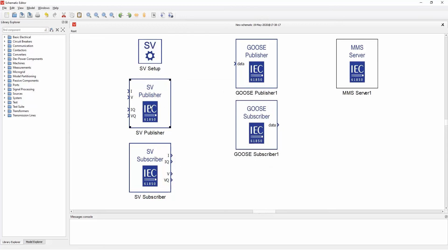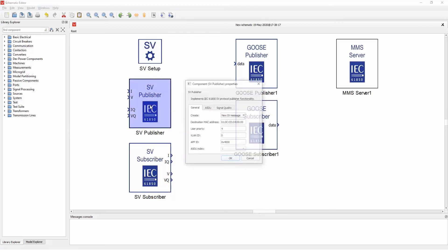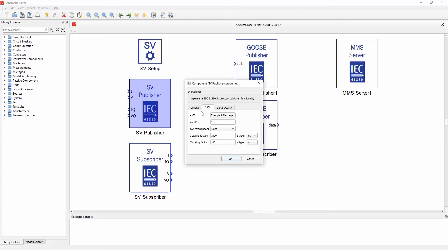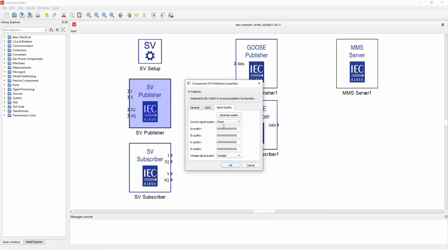If we go to the publisher, you can define all the message fields. So we have destination MAC, user priority, VLAN, and so on. I will not go into details, but you can also specify the application specific data unit, the ID, configuration revision, synchronization, scaling type, and signal quality, which can be either through a variable as it is right now with terminals, or it can be a fixed value where you specify for each signal the quality.